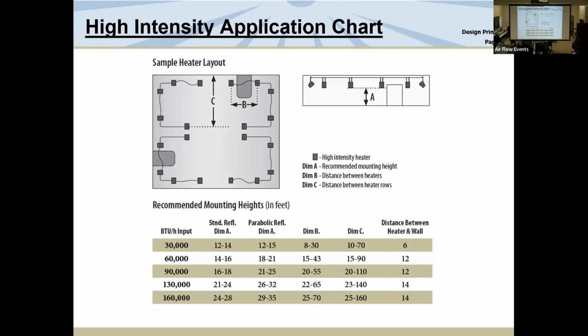Next slide, please. And the basics behind this, as I'm looking at it, would be: match where the load is, not where the people are. So the primary thing with infrared that we try and push is perimeter mounts. Okay, and then I think you also have to be mindful of where the people are, because we're allowed to zone heat with infrared. So yes and no. If it's total building heat, go perimeter first, center second. Got it. But if it's spot heating for comfort, have a roof load, right? Yep, that's where the people are too, underneath the roof.